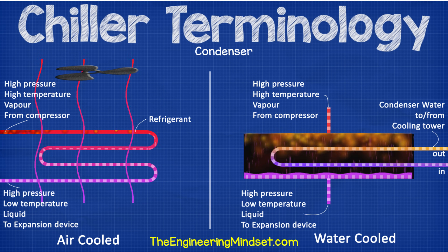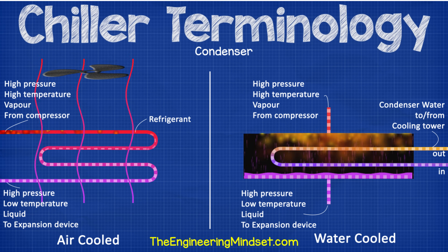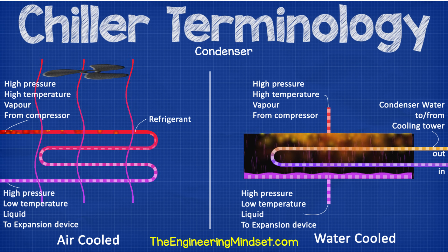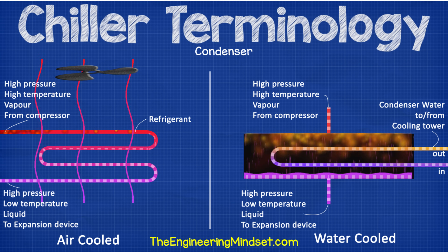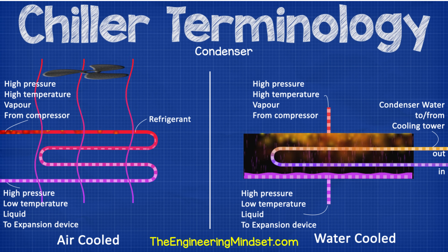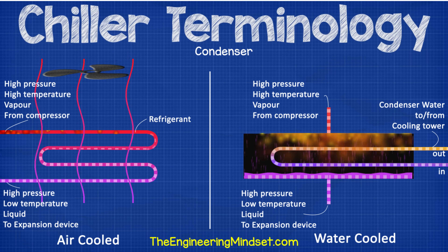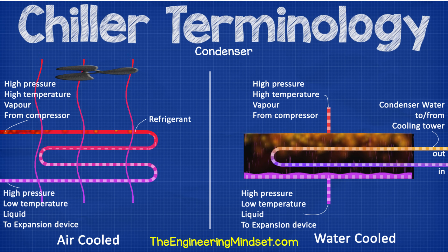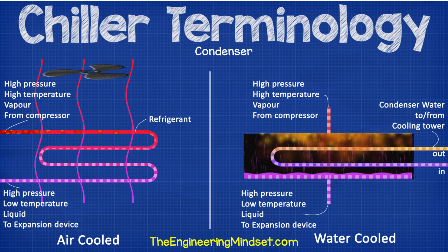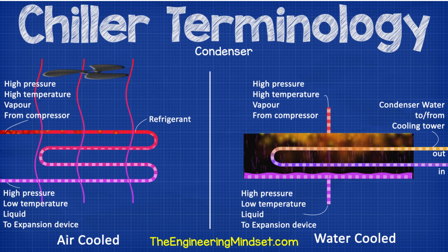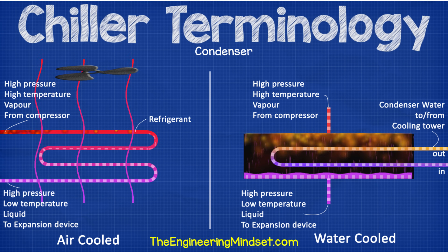Condenser. This is where the unwanted heat of the building is rejected to the atmosphere, either through an air-cooled or water-cooled condenser. The refrigerant, which carries the unwanted heat from the evaporator over to the condenser, will enter as a high-pressure, high-temperature gas, and as the thermal energy is rejected, it will leave as a high-pressure liquid.